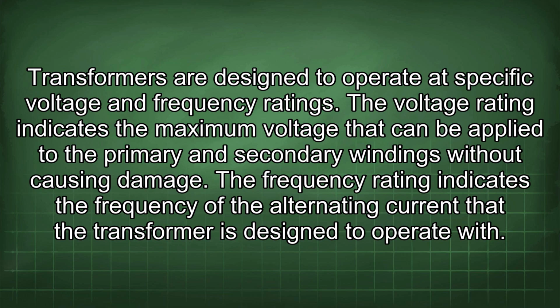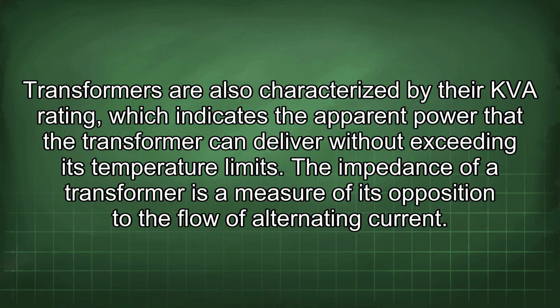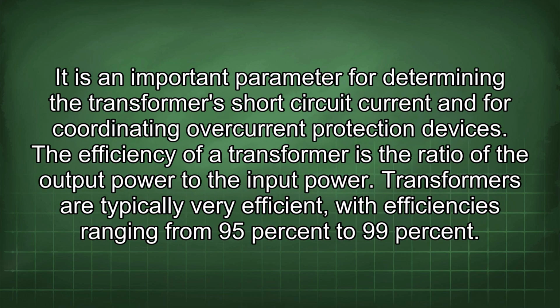Transformers are designed to operate at specific voltage and frequency ratings. The voltage rating indicates the maximum voltage that can be applied to the primary and secondary windings without causing damage. The frequency rating indicates the frequency of the alternating current that the transformer is designed to operate with. Transformers are also characterized by their kVA rating, which indicates the apparent power that the transformer can deliver without exceeding its temperature limits. The impedance of a transformer is a measure of its opposition to the flow of alternating current. It is an important parameter for determining the transformer's short-circuit current and for coordinating overcurrent protection devices.